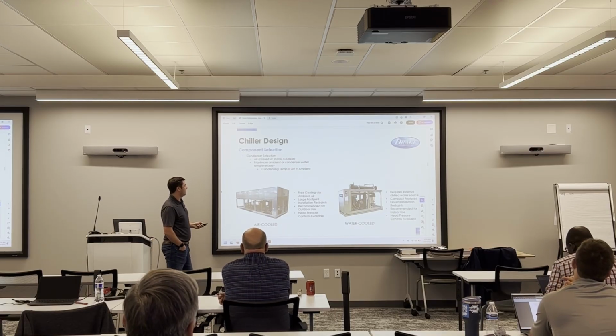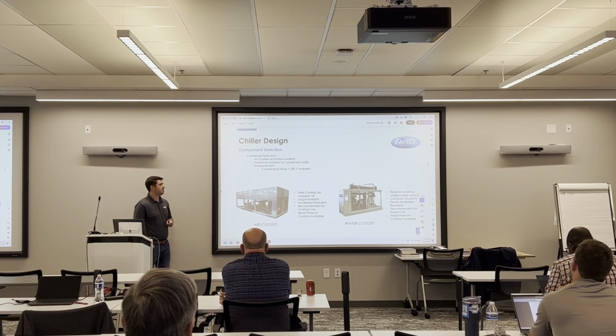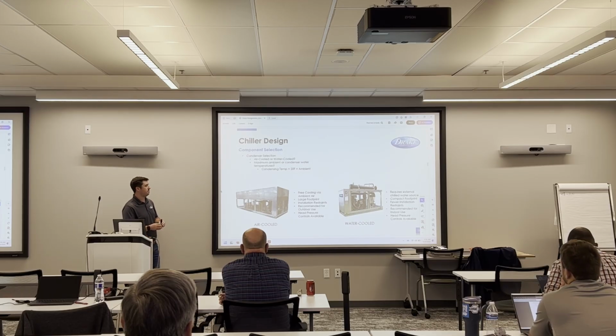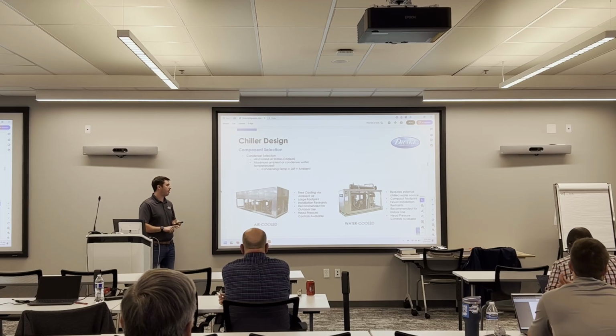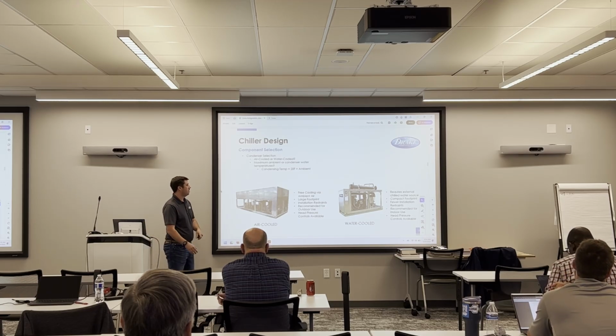The downside of an air-cooled unit, it's got a large footprint. As you can see, these things can take up a decent amount of space. Our largest condenser is about 30 feet long, I would say, so it's going to add to your footprint. What's nice with air-cooled designs, though, is if footprint's an issue, you can generally split the unit. So you can put the condenser up on a rooftop, and you can put all your other components, like your compressor, evaporator, metering device, indoors.